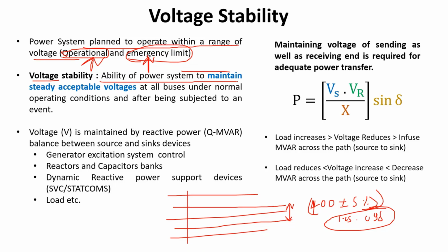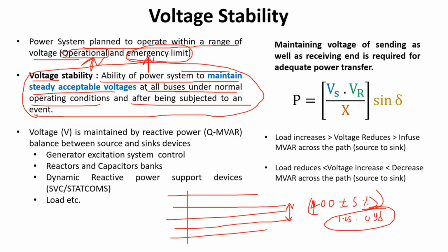It is the ability of any power system to maintain steady, acceptable voltage at all buses under normal operating condition and after being subjected to an event. So normal operating condition as well as after any event. In the Indian power system, we consider one event as the n-1 condition. Whenever there is a tripping of one equipment or one transmission line, your voltages should still be within the acceptable limit. And that acceptable limit is defined by the operational limit. So your voltages should be within the operational limit without any changes in the system. Let us say one transmission line trips, still your voltage should be within that operational limit. That's the criterion that has been provided. We will look into those things.